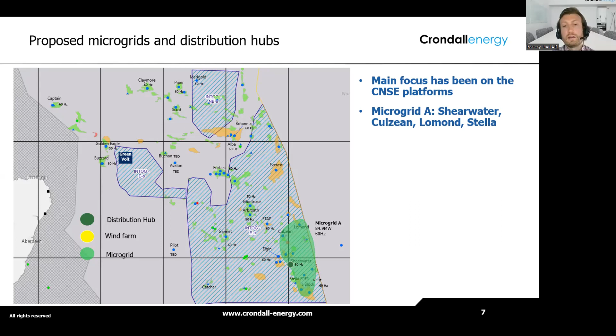We then have Microgrid C, which is for Elgin Franklin. It's for a single facility because it's got a high power demand. We then have Microgrid D, which is for ETAP, Gannet, and Monarb. You'll notice here that Monarb's a 50 hertz facility. Now, what we're looking at with these is we're doing all of the frequency conversion on the distribution hub, on our microgrid facilities, so that the consumer, Monarb, is going to receive the power at the right frequency and the right voltage for them. So there's no need to perform any conversion on board their facility. So we're trying to minimize the brownfield mods for them.